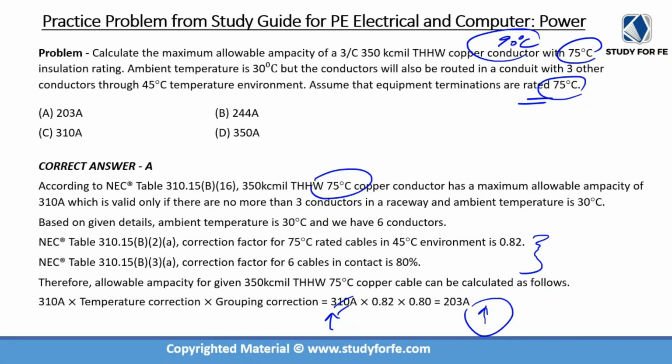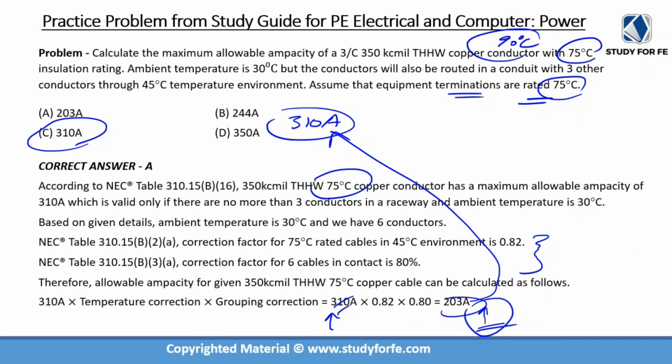But the limit to that is this higher ampacity, whatever you end up with, can still not be greater than the 75 degree C rated allowable ampacity, which happens to be 310 amps. So this 310 amps is the absolute maximum that you can have with the equipment terminations that are 75 degree C. But you get to start with a higher allowable ampacity, and maybe the number that you end up with will be somewhere in between 203 amps and 310 amps, but it cannot exceed 310 amps because you're limited by the equipment termination.